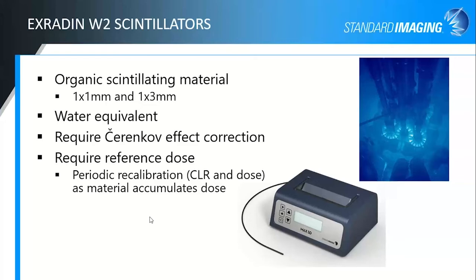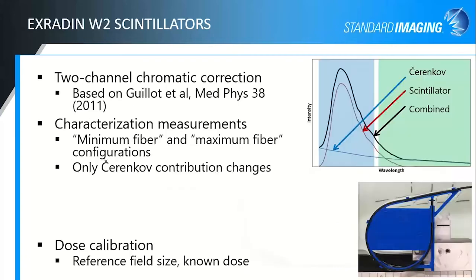But it's not an absolute dosimeter like an ionization chamber is that can be calibrated. It is a relative dosimeter, so it does need periodic recalibration, characterization type measurements, because the plastic does degrade as the material accumulates dose, and so your signal level will decrease slightly. We use a 2-channel chromatic correction to get rid of that Cherenkov.